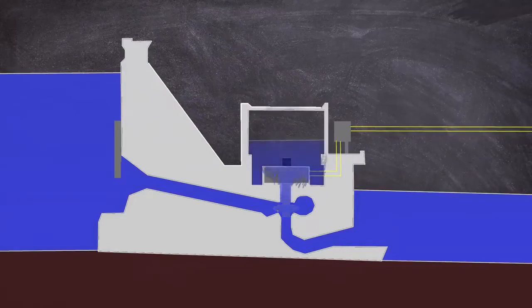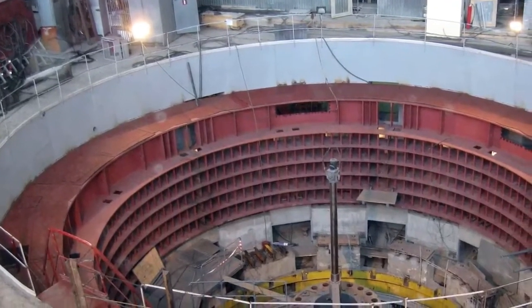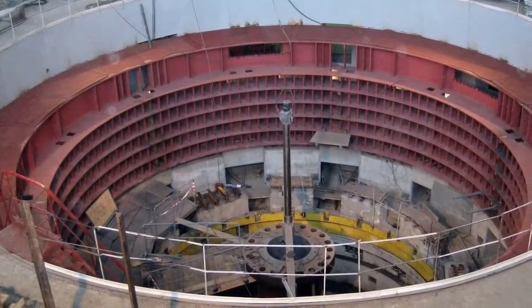The water soon cut through the structural steel and the turbine gallery roof collapsed. Workers were washed away out of the building and down into the river; some were later rescued, but others were sadly not. The steel gates to the water intake pipes of the turbines, weighing around 150 tons each, were closed manually — held up by hydraulic jacks — a process that would take at least 25 minutes, all while water continued gushing out of the destroyed unit 2. The emergency diesel generator was started and the spillway gates of the dam were opened. Units 7 and 6 continued to operate after their safety shutdown systems failed to trip, becoming submerged and causing damage to equipment and structures. Units 2, 7 and 9 were completely destroyed, with the remaining units experiencing serious damage.